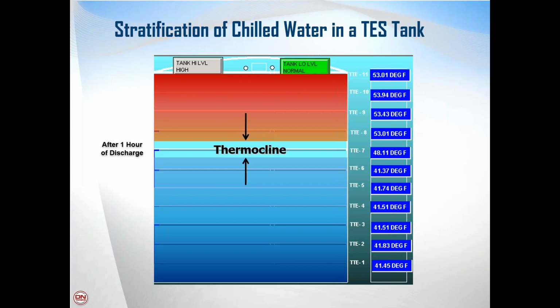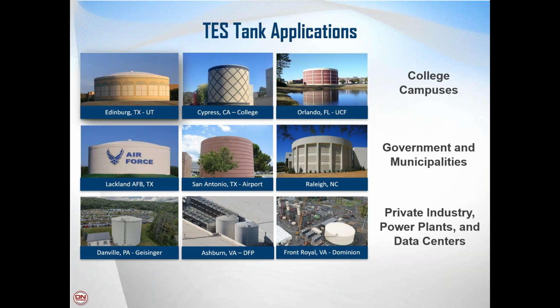Yeah, so the insulation thickness on the outside wall of the tank is designed specifically to ensure a limitation on the amount of heat gain to the chill water inside. So all of these tanks that you're looking at here are all insulated on the exterior. And even the tank in the very center, which is our oldest tank, as we've mentioned before, it's going on its 39th birthday, that insulation is original on that tank. And because there is a cement-like coating over the outside to prevent it from degrading over time.